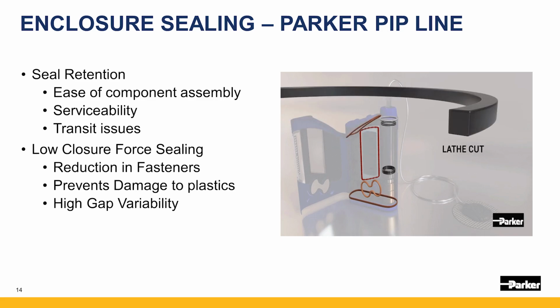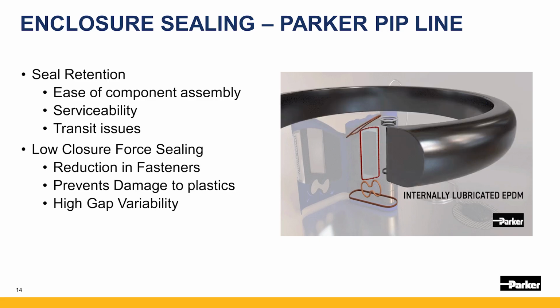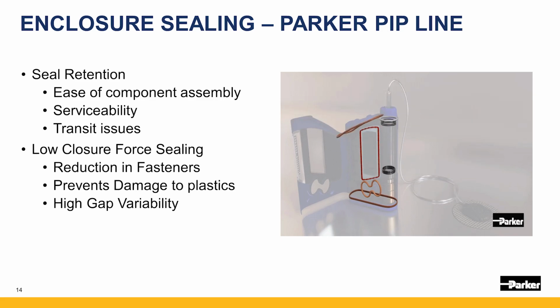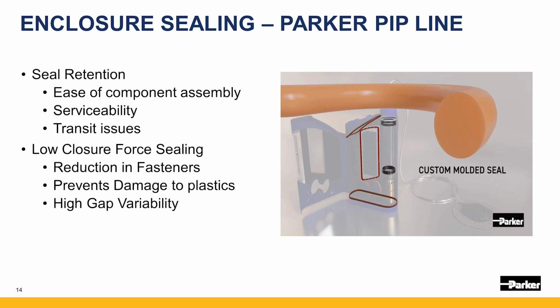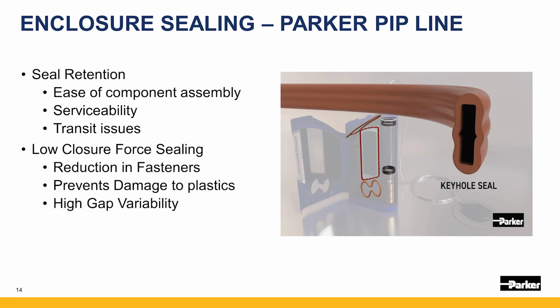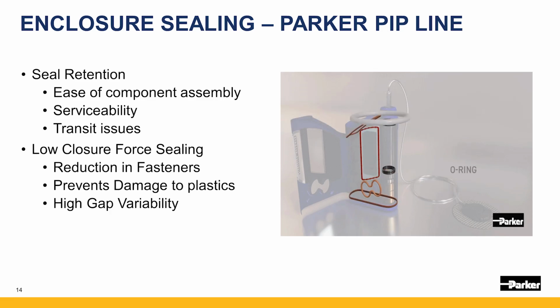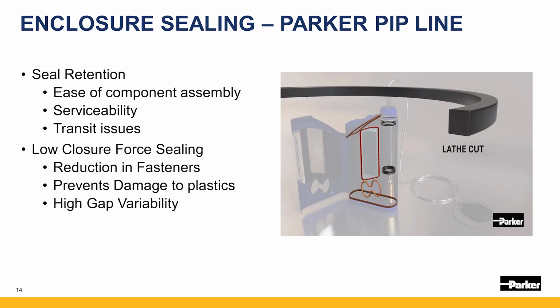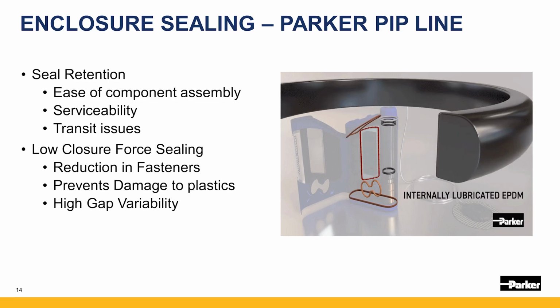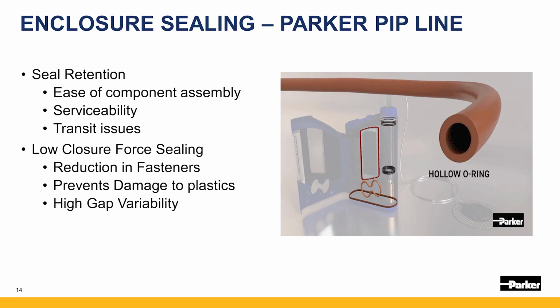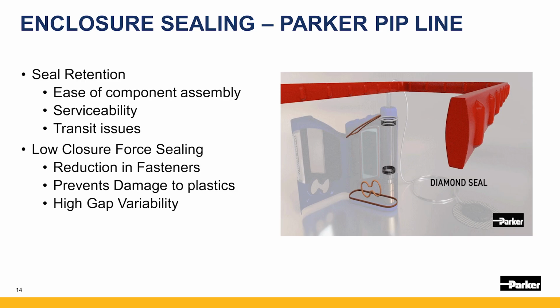Secondly, low closure force is important for various reasons. First, it reduces the amount of fasteners or screws needed to close a device, which can be a cost saving in manufacturing hardware. Second, it protects the hardware from damage through the high force needed. Lastly, the seal provides high gap variability. They are able to overcome higher tolerances or higher flatness variances, usually seen when manufacturing using plastics.